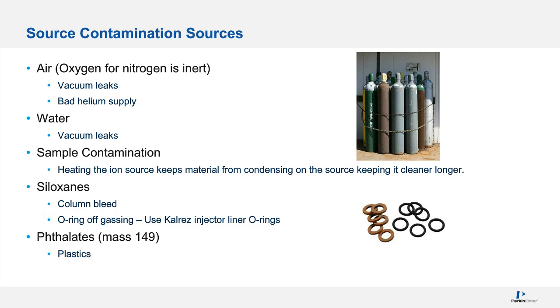Phthalates from plastics. I dealt with that. I contaminated my system with plasticizers. It's mass 149. Some of these contamination compounds have nice, unique masses. I do not let anything touch plastic that I put into my system. I won't even use the squeezy bottle to fill my wash vials. That's how paranoid I am. Whatever's going into my system is glass, especially if I'm looking at below picogram, sub-ppb levels. I don't want to see this type of contamination. If it's not interfering with your compound, though, I understand. Who cares? But I just like to be more careful.